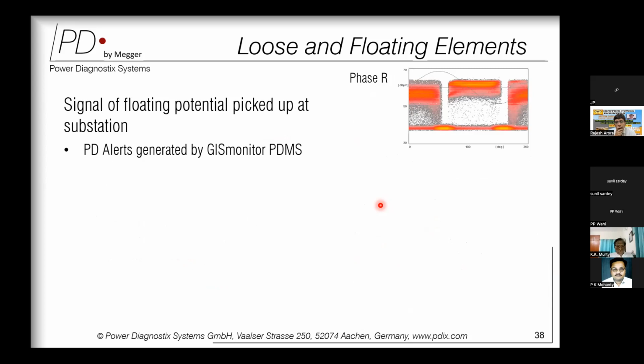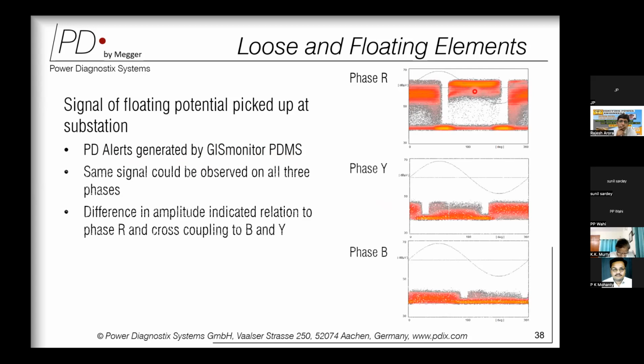Let's take an example of a typical case study we had at a particular substation, where a PD alert was generated by the instrument on R phase, like we see a signal over here. Fortunately it is a multi-channel instrument, so we see the same pattern acquired on Y phase as well as B phase of the parallel sensor, which helps us understand that the same signal on R phase is translated or coupled to Y and B. So on a particular sensor, say sensor point number 4 on R, Y and B, the pattern is observed on all three phases, more or less similar.